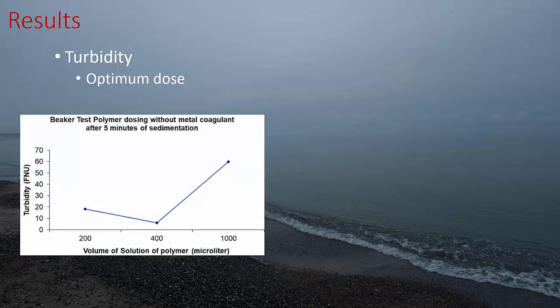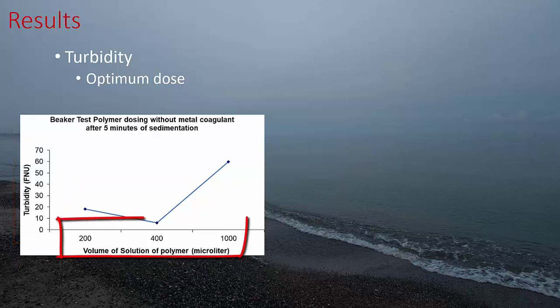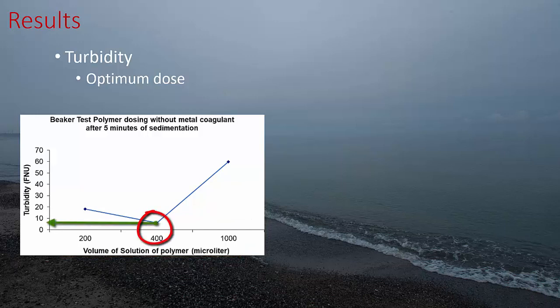You try to find an optimum dose with the lowest turbidity. In this case I did a test where I looked at polymer dosing without any metal coagulant — just polymer. On the y-axis is the turbidity after sedimentation; on the x-axis is the polymer dose. To get the lowest turbidity the optimum dose here was 400 microliters. But 400 microliters might be too much, so if the turbidity at 200 microliters is acceptable, you might be able to reduce the dose to 200.